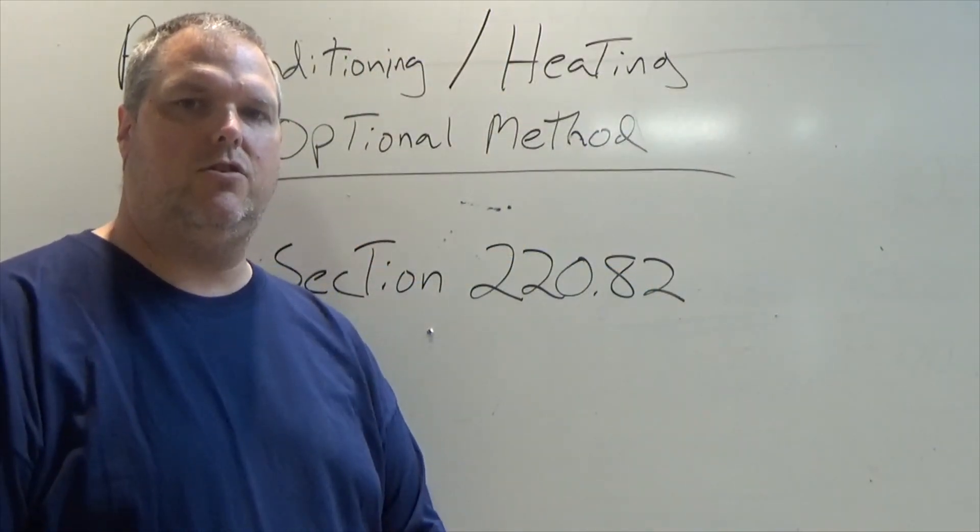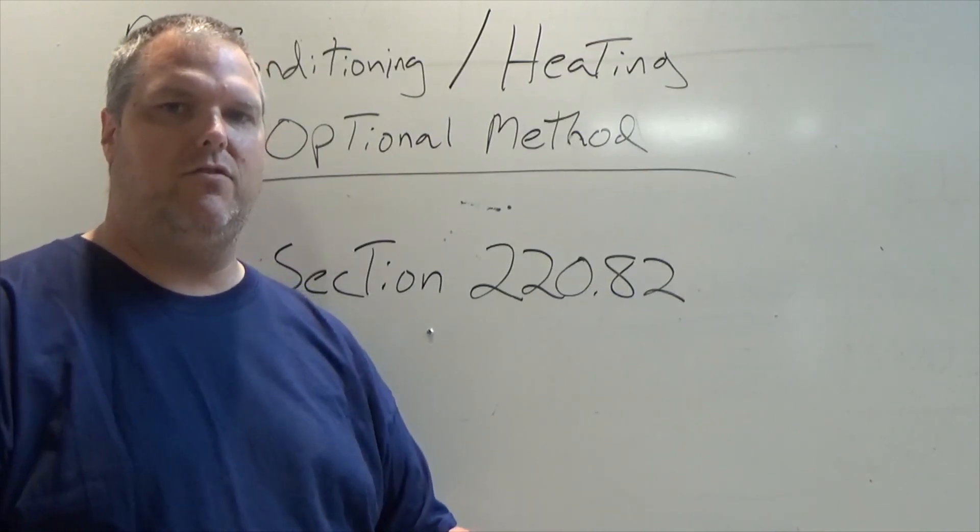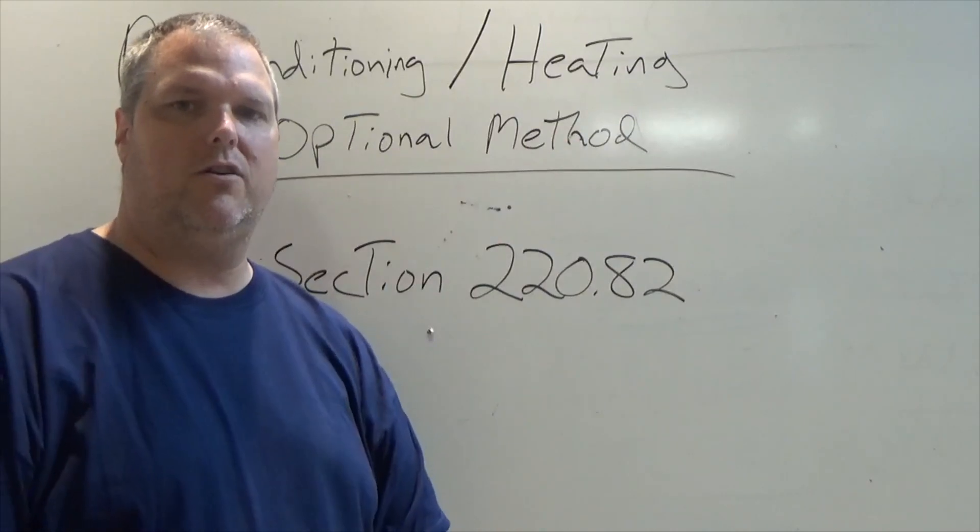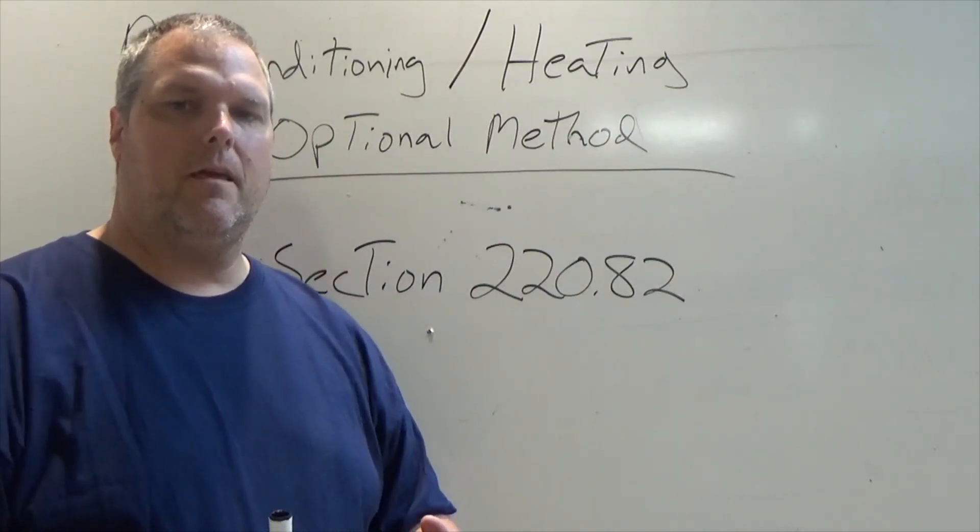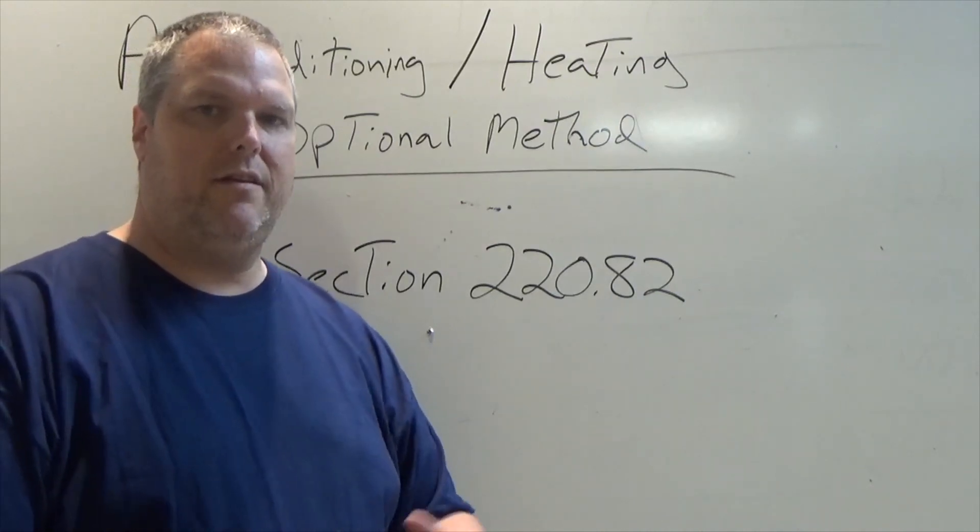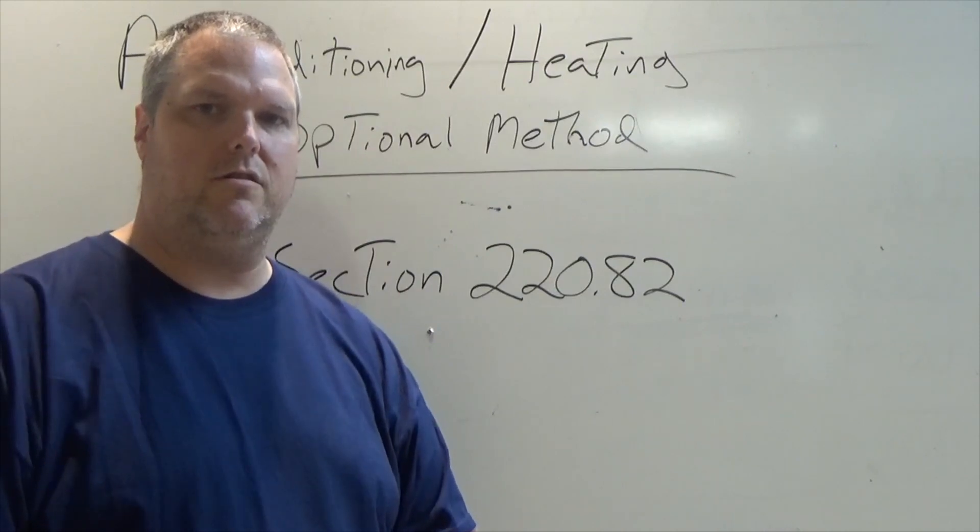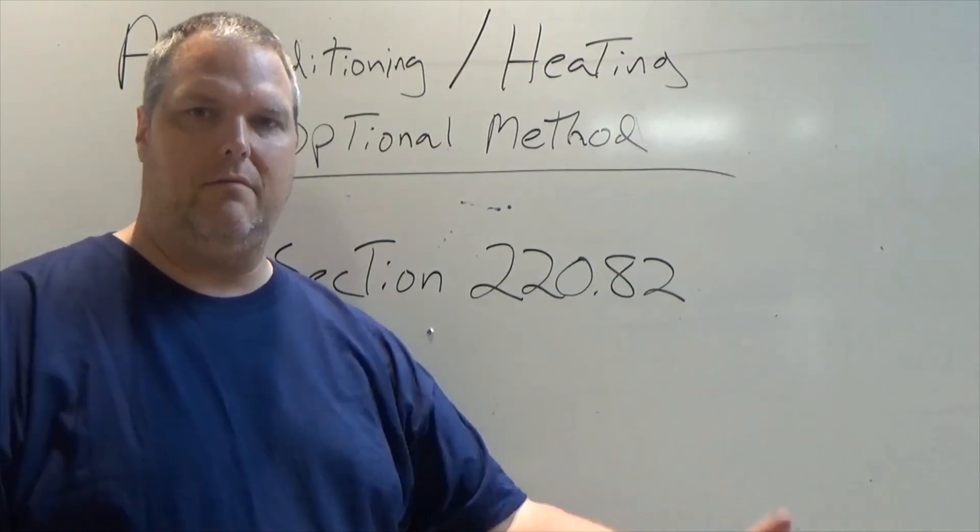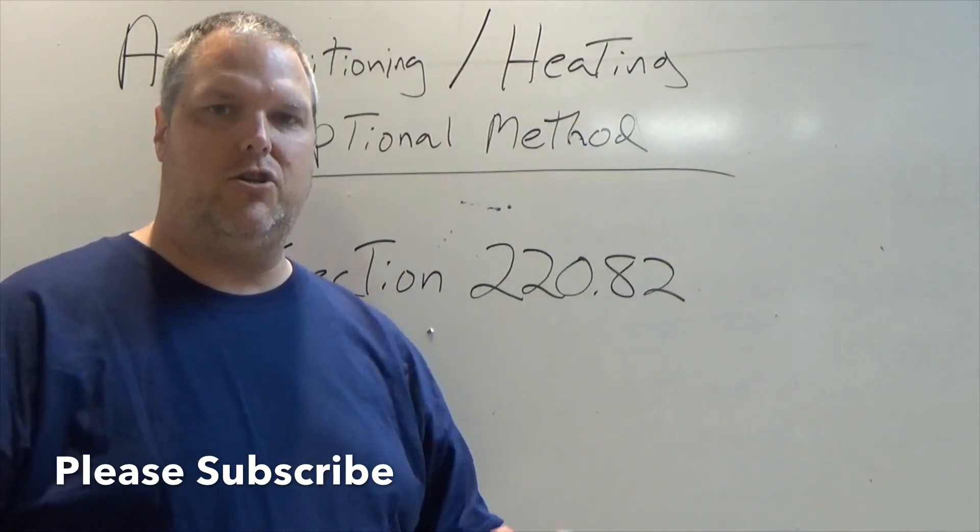Section 220.82 is what we're going to be discussing, the optional method. We talked about this in my first video. If you haven't seen it, click the link above, watch my first video showing you how to find general lighting demand. The optional method and the standard method are two different types of calculations. One is looking for more of a breakdown with a standard calculation. The optional method is basically taking our calculation, adding a bunch together, coming up with different demand factors, and then coming up with a different solution.